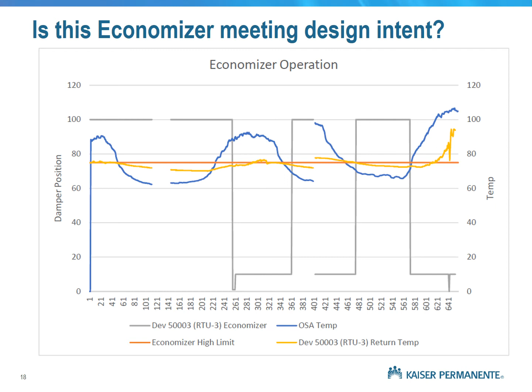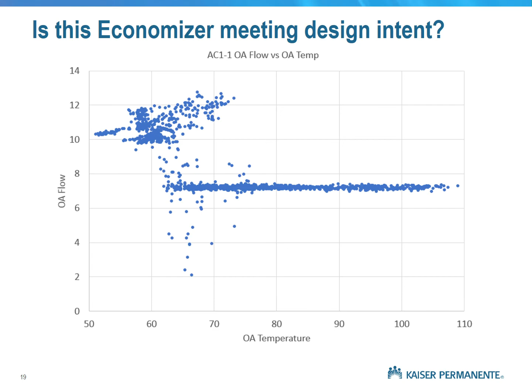Something like this. This is a different project, by the way. So on the y-axis we have outside air flow, not damper position, but we do have outside air temperature on the x-axis. And by the way, I have no idea what the units are on that outside air flow point, because this is a 20,000 CFM air handler, so I don't know what 8 or 10 is. But this is a whole lot easier to look at, right? I mean, you can see right away, anytime the outside air is over 80 degrees, we're obviously at minimum position. Well, that's good. But what about down there when it's below 70 degrees? Well, what you really want to see is outside air minus return air. That's when the economizer is supposed to be working.